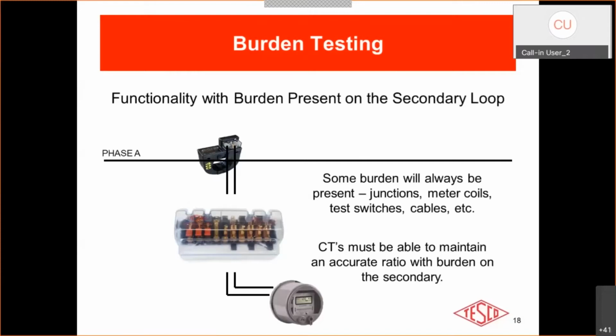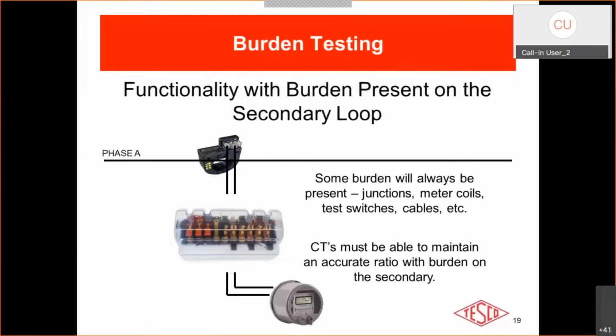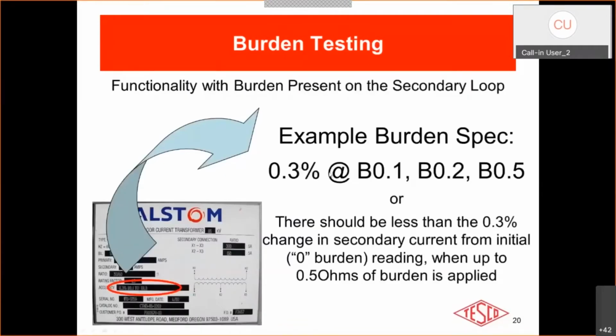The burden specification that we showed above in this example, 0.3% at burdens of 0.1, 0.2, and 0.5 is essentially saying that the CT manufacturer will guarantee the accuracy of the CT ratio as long as you do not apply more than 0.5 ohms of burden on the secondary. Otherwise stated, there should be no more than a 0.3% change in the secondary current from the initial current reading when up to 0.5 ohms of burden is applied.